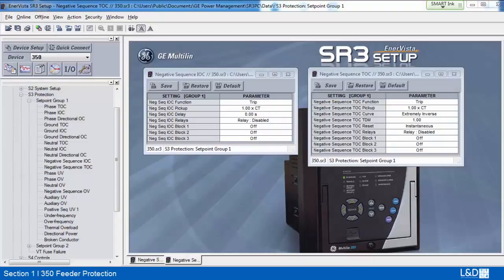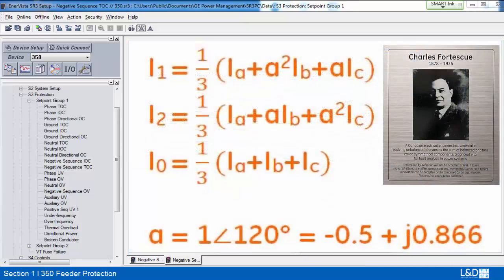Negative sequence IOC and TOC have the same settings as phase and neutral IOC and TOC. The difference is that the input is the calculated negative sequence current. The negative sequence overcurrent elements are uniquely suited to detect the negative sequence current present in an unbalanced load. The pickup setting should be above the maximum expected negative sequence current due to load unbalance. Let's review the calculation of symmetrical components of the current by the Fortescue formula, as introduced in FMPR 103.